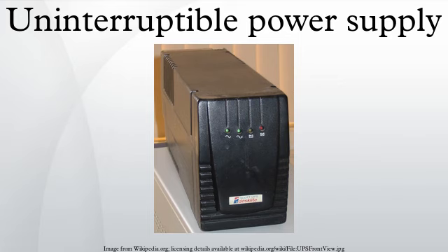Ferroresonant units operate in the same way as a standby UPS unit. However, they are online with the exception that a ferroresonant transformer is used to filter the output. This transformer is designed to hold energy long enough to cover the time between switching from line power to battery power and effectively eliminates the transfer time. Many ferroresonant UPSs are 88% efficient and offer excellent isolation. The transformer has 3 windings, one for ordinary mains power, the second for rectified battery power, and the third for output AC power to the load.